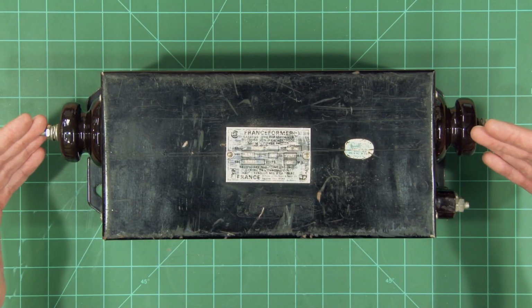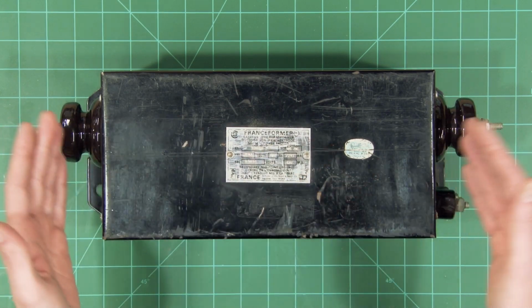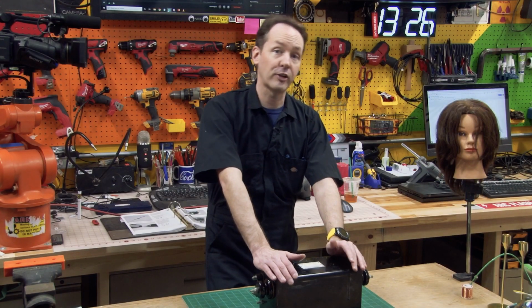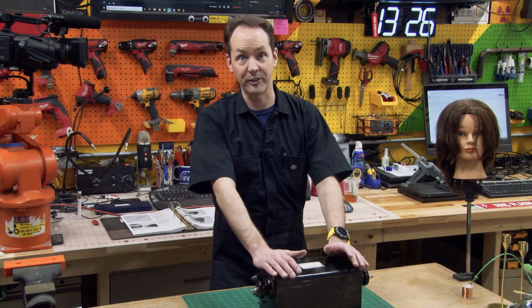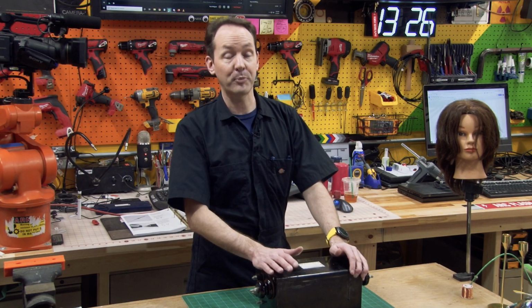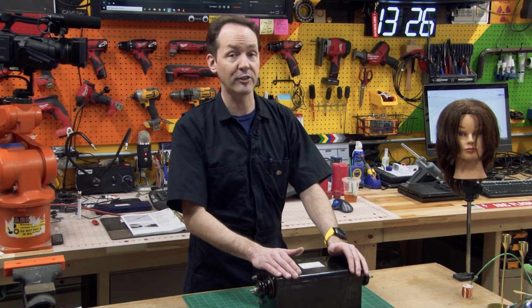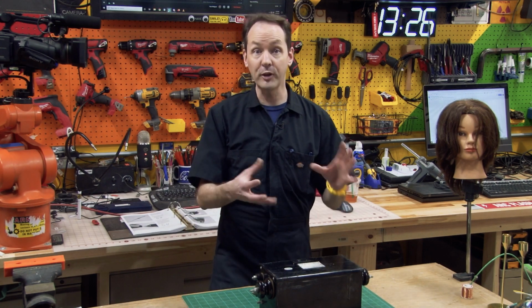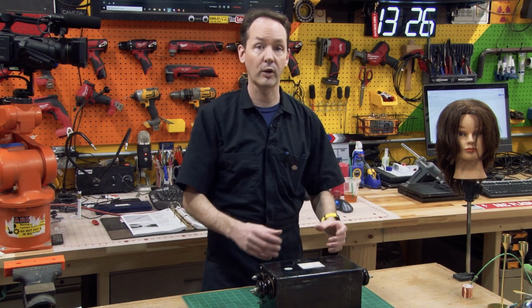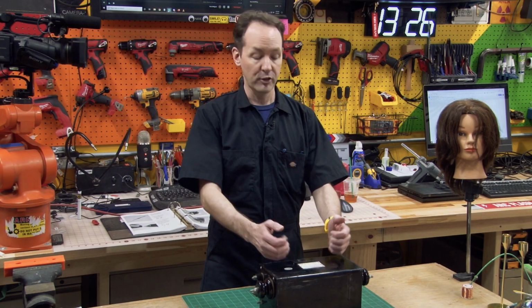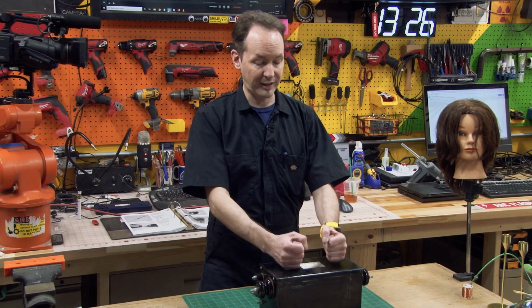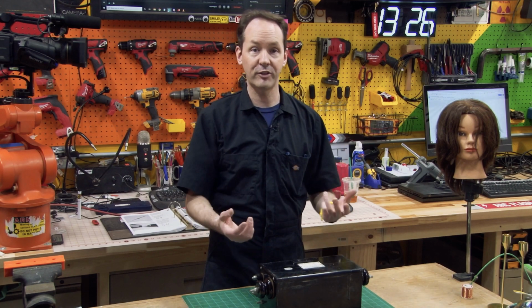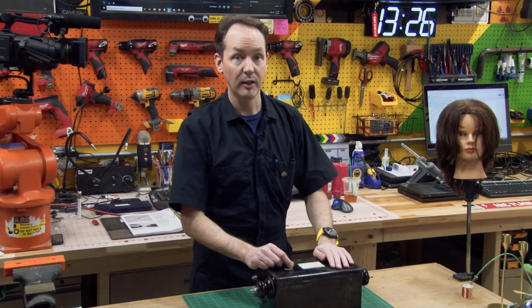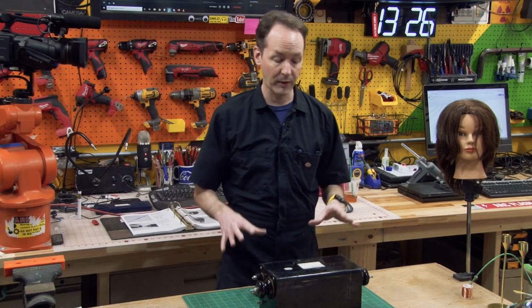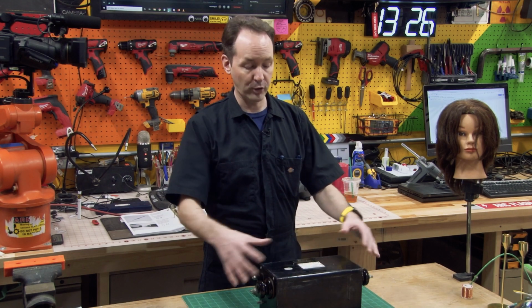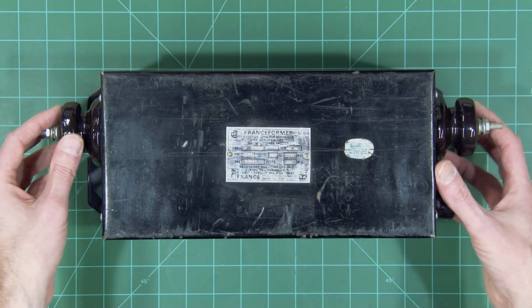As we look at our transformer, you'll notice there are terminals on both ends. Not all neon sign transformers have their terminals arranged like this. They come in a million different flavors, and especially at lower voltages, the terminals will be in different spots. Frequently they're all on top or all on one end, or high voltage terminals might come just as cables coming out from inside. I've seen them with screw terminals deep down inside where you have to take a cover off to get to them.